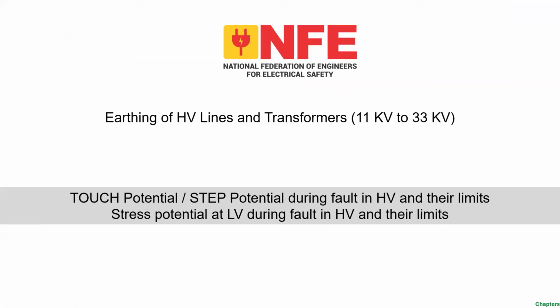Good morning, all participants. Today we are going to discuss a confusing subject, or a subject which is of a lot of interest but sometimes creates a lot of confusion among electrical engineers. We are going to talk about the earthing of high voltage lines and transformers, especially between 11 kV and 33 kV. That means you have a distribution transformer, the primary side is 11 or 33 kV, and the secondary side is a low voltage installation. Maybe a distribution transformer or maybe a transformer in an industrial or commercial premise.